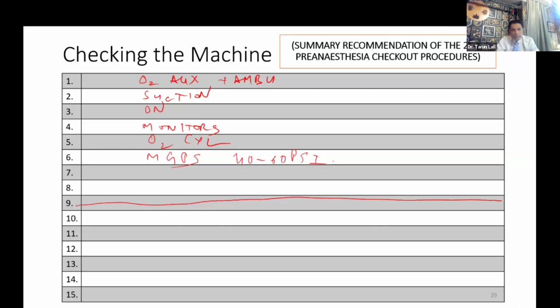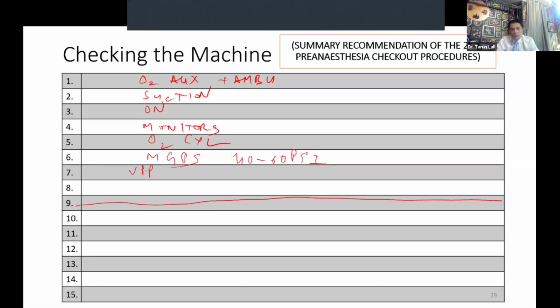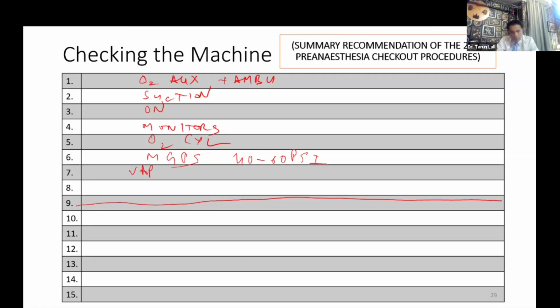Next, I come to the vaporizers. So I see that there is an adequate amount of agent in each of the vaporizers, and I should also see that I am not able to turn on two vaporizers simultaneously. That is your selectatec mechanism. So sometimes what happens is that if the vaporizer has moved slightly or if it has been changed recently, then it might not be aligned properly, which will allow you to turn on two vaporizers simultaneously, which can be quite harmful. So this is one check that I would like to do at this stage.